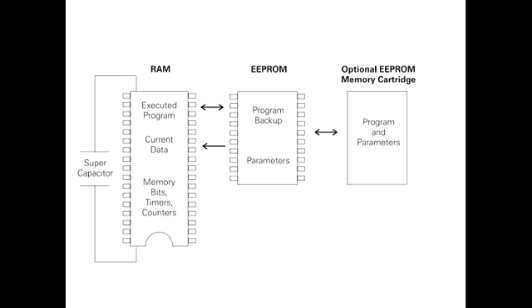Supercapacitor: A supercapacitor, so named because of its ability to maintain a charge for a long period of time, protects data stored in RAM in the event of a power loss. The RAM memory is typically backed up on the S7-221 and 222 for 50 hours, and on the S7-224 and 226 for 190 hours.